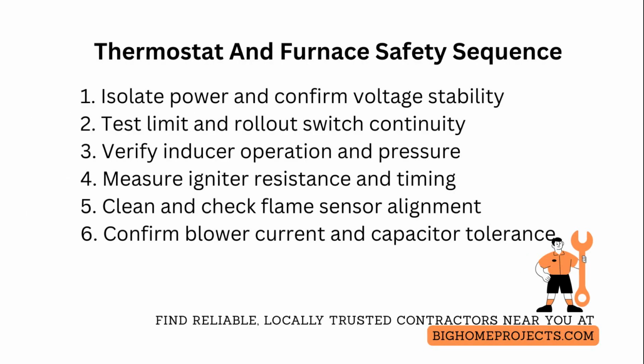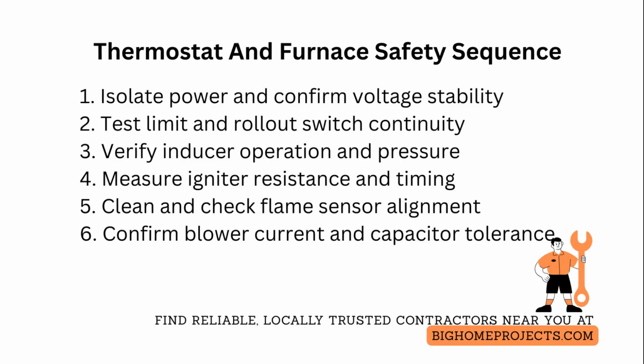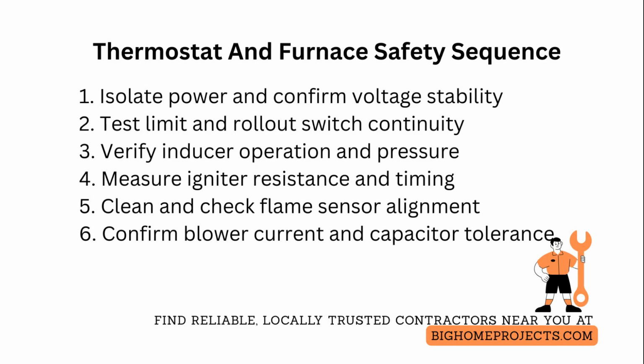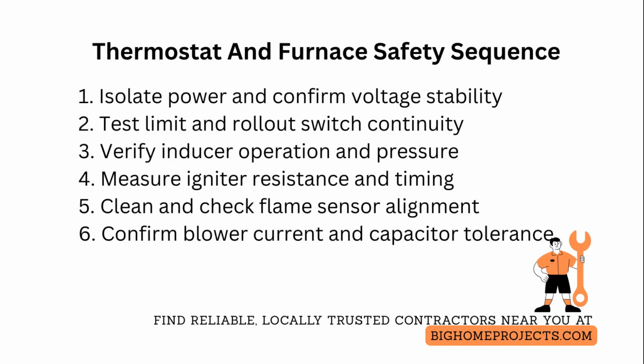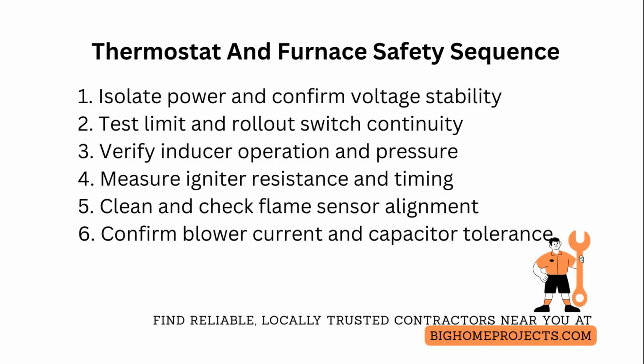Start by isolating power and confirming line and neutral integrity so the control board receives stable voltage. A sagging supply will cause false safeties and erratic blower starts. Next, the control board reads the open or closed status of limit switches and rollout switches. Teach technicians to test continuity under both cold and heated conditions, and to inspect for corrosion, loose splices, and proper placement against the heat exchanger.